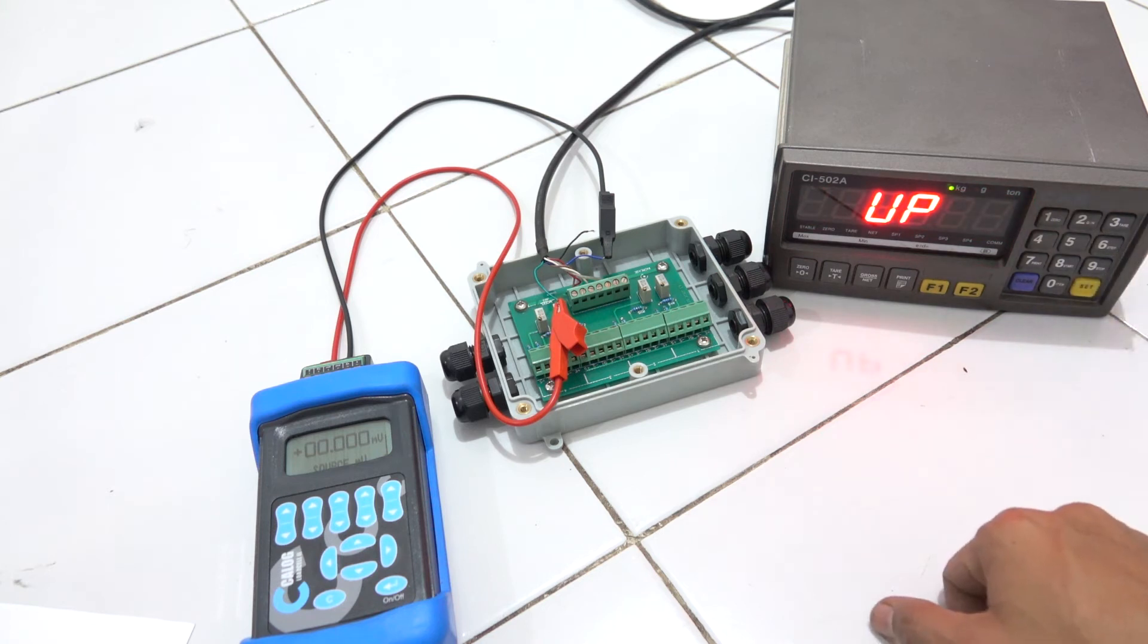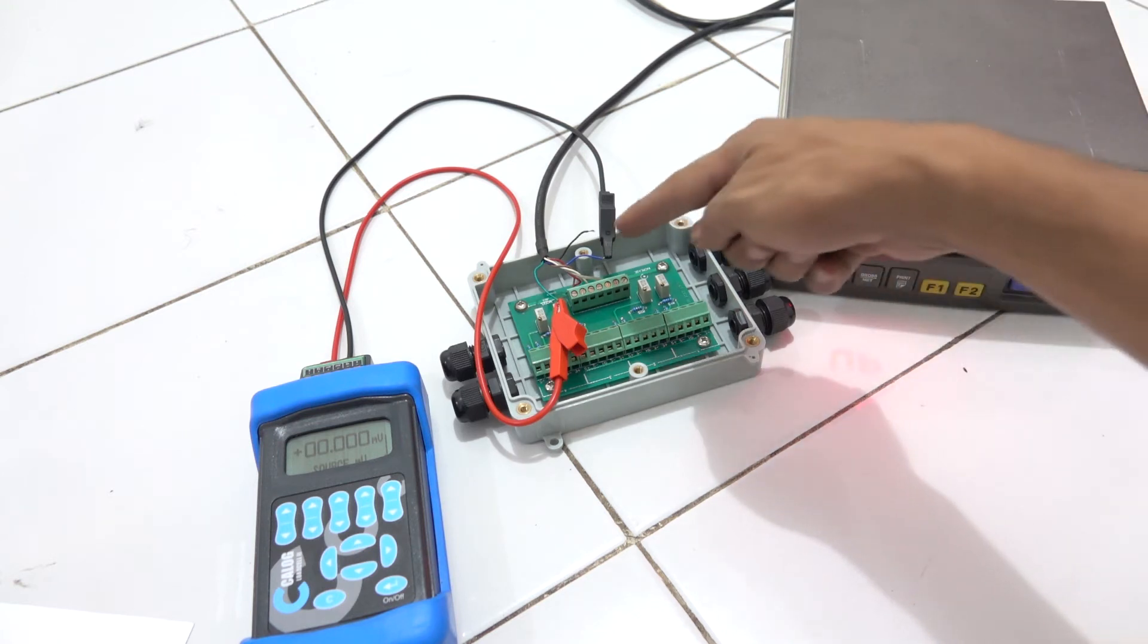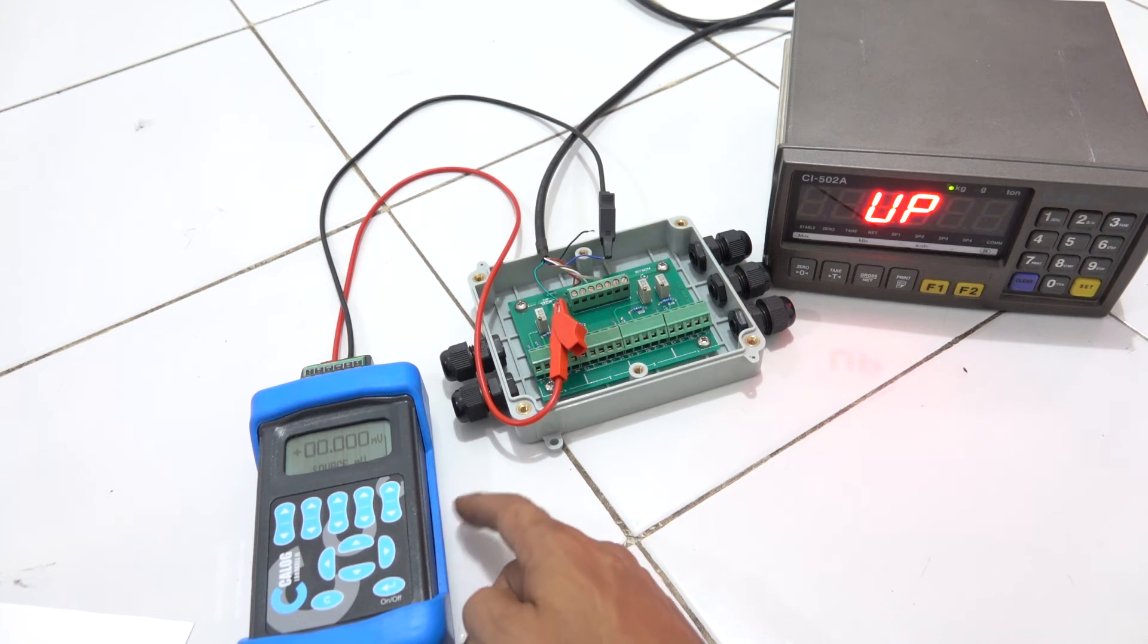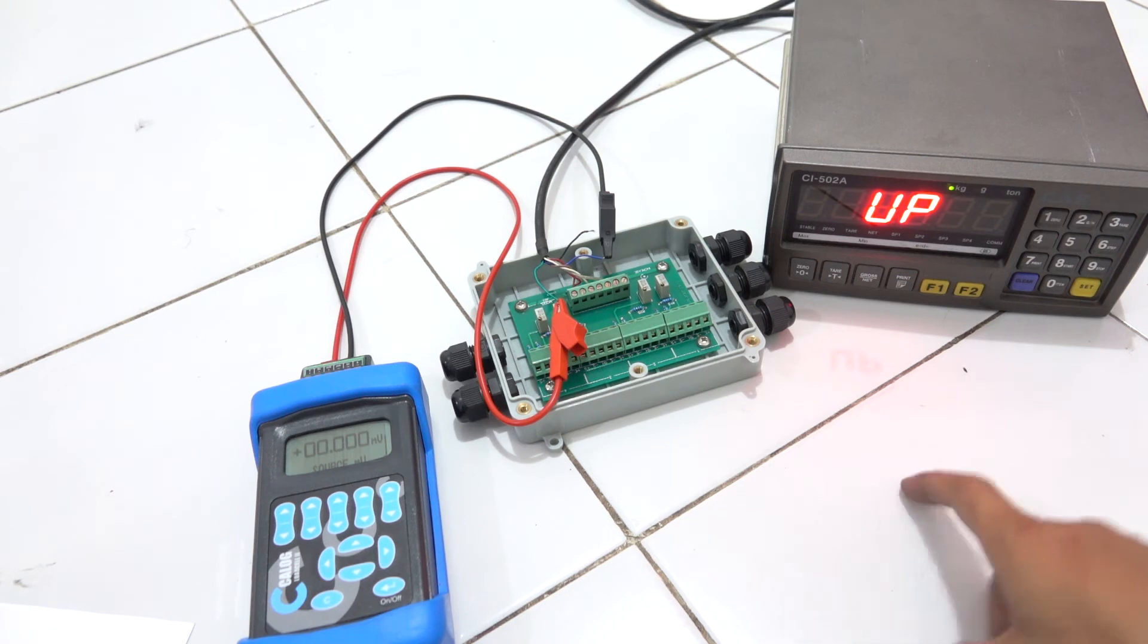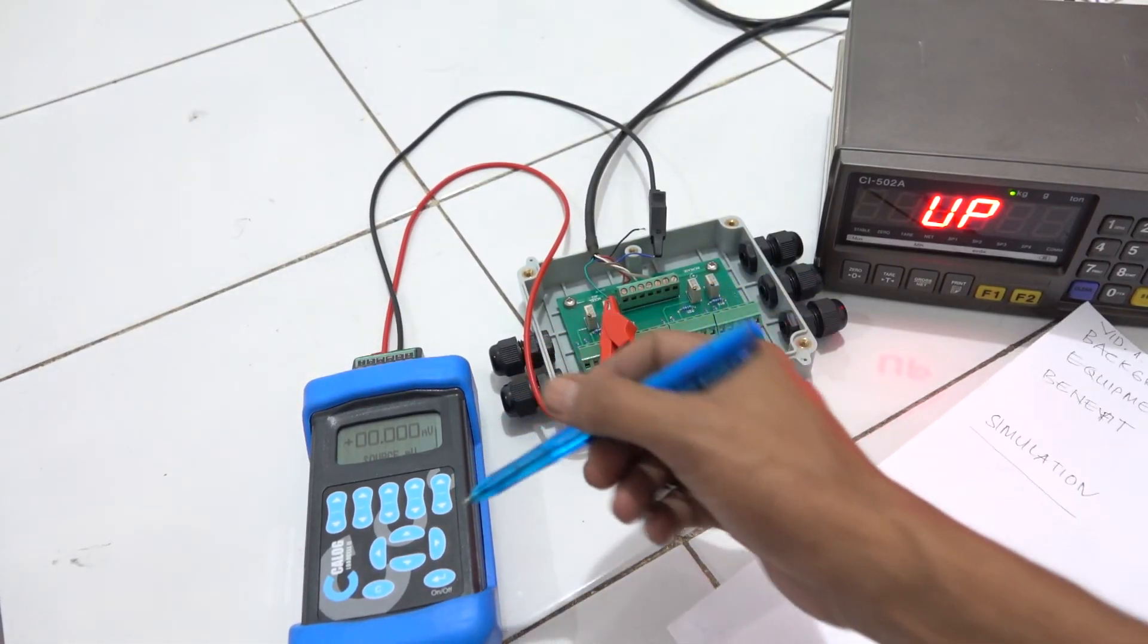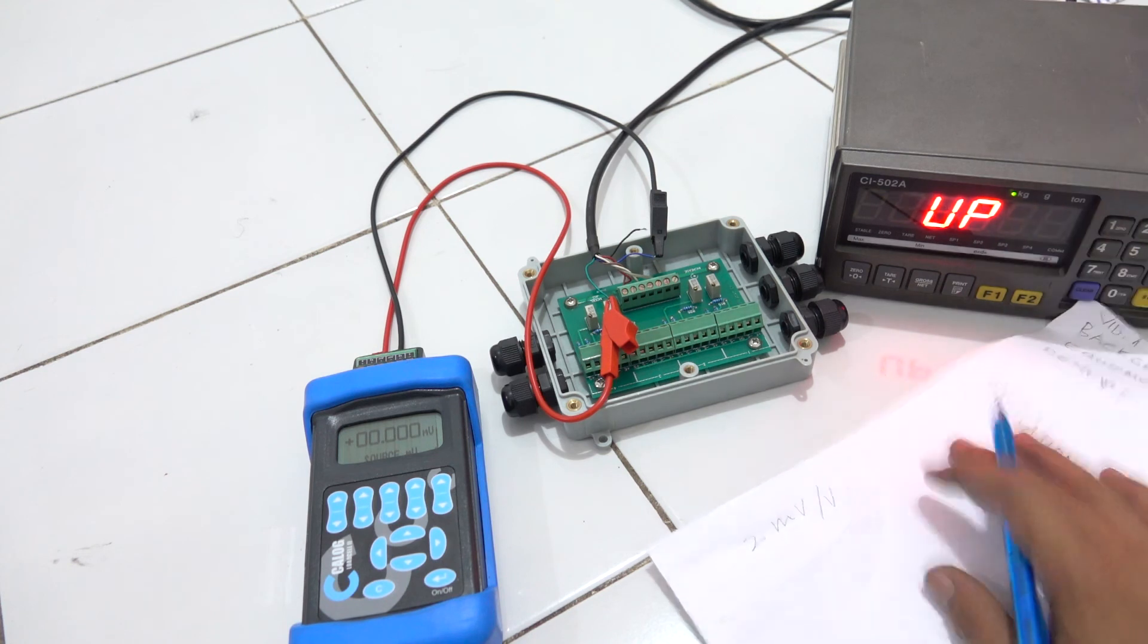Now the challenge is here. This load cell indicator generates excitation voltage to here - 10 volt. So imagine that this load cell - but actually now using Calc - imagine the load cell specification is 2 millivolt per volt. It means single load cell, it means 20 millivolt generated at full capacity. Maybe you can make a simple calculation here. Let's say this load cell has 2 millivolt per volt, and this can generate excitation voltage 10 volt.